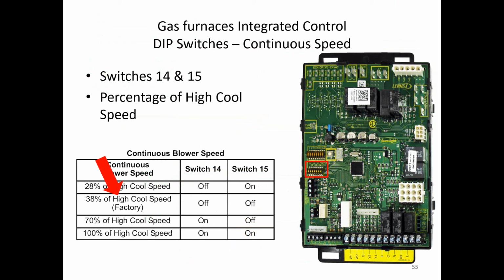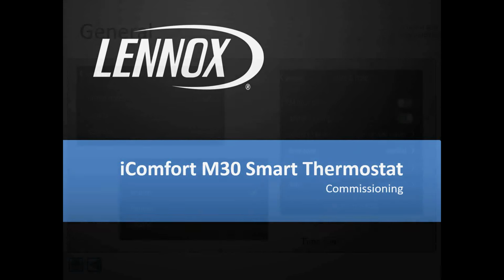I apologize for that. On the furnace control, we talked about this yesterday. Please note that the factory setting on the furnace control is 38% demand of the cooling blower. It's operating between 28, 38, 70, and 100% as the options. So you want to select that option. Again, this is more for IAQ type control.